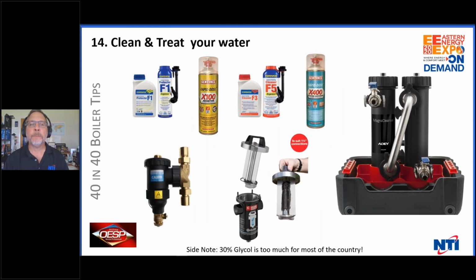I always thought this was something like looking for Elvis. Dan Holohan wrote about oxygen infiltration, an article years ago that was entitled Looking for Elvis. I never thought for an instant that you needed to clean and treat a system. I can tell you without a doubt, it has to be done for all boiler installations. Cast iron, aluminum, copper fin, I don't care what you have for a boiler, stainless steel condensing, it needs to be flushed and cleaned and then treated.